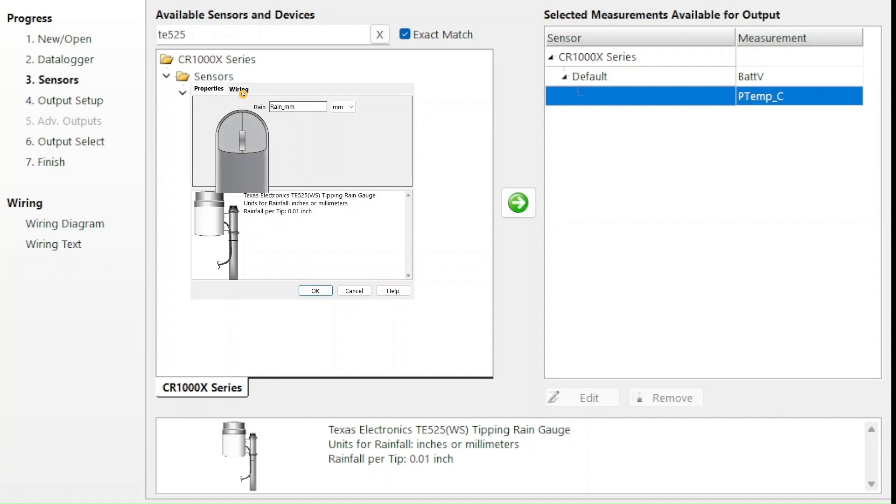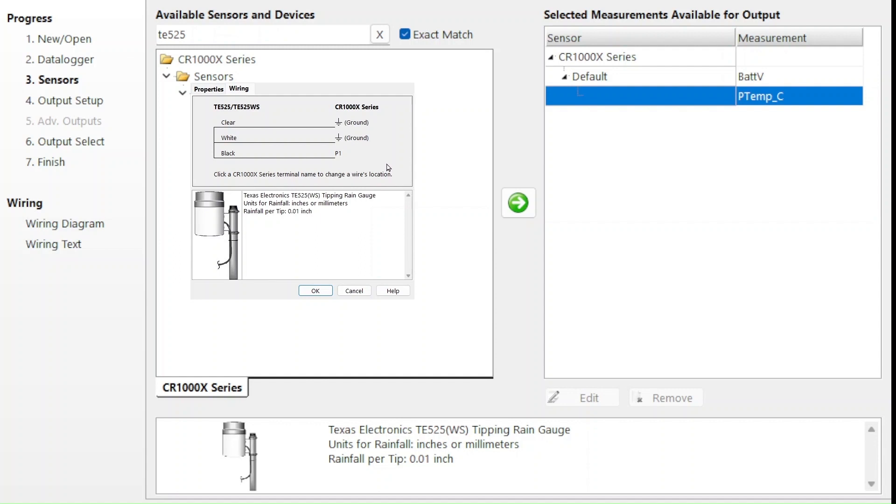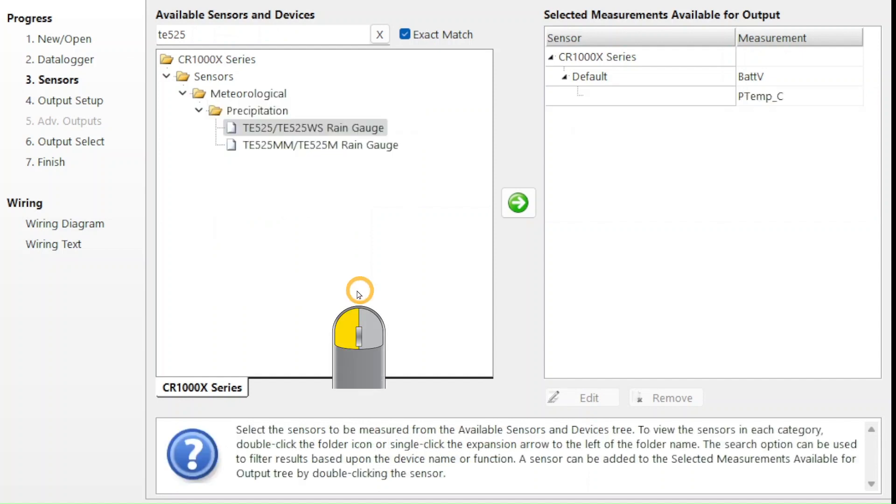I want to see how SCWIN assigned the wiring, so I select the wiring tab. The wiring information shows that SCWIN wants to connect the black wire to P1 and the white wire to ground. That doesn't match what I see for channel 1H, so I know that the first sensor can't be the TE525 rain gauge. I select Cancel to close this window.